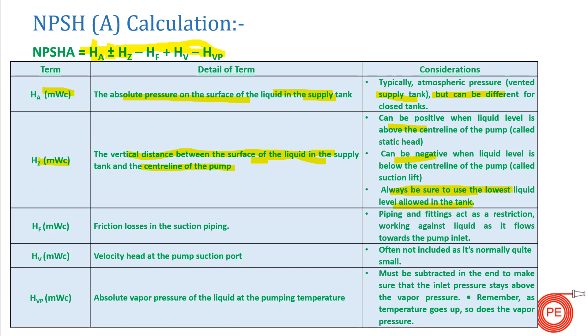The next term is HF — frictional losses in the suction piping. Whenever a pump is sucking from a tank, there are many fittings involved in the piping system up to the pump suction port. There will be frictional losses in those fittings. HF is subtracted from HA plus or minus HZ, so the frictional losses occurring in the piping system up to the suction port of the pump represent HF.